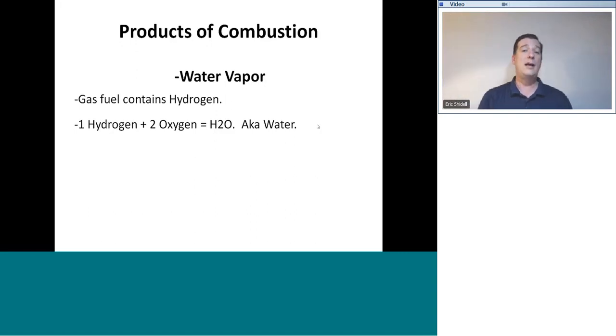This is also why condensing appliances work. Condensing appliances such as furnaces and water heaters and boilers that have an annual fuel efficiency rating greater than 90% will have a water drain because they are extracting so much heat from those flue gases, they will cool to the point of condensation, and that's intentional. In other appliances, condensation is not intentional. And condensing in, say, a brick chimney or a metal flue will lead to extreme corrosion and failure of that flue and of that vent.